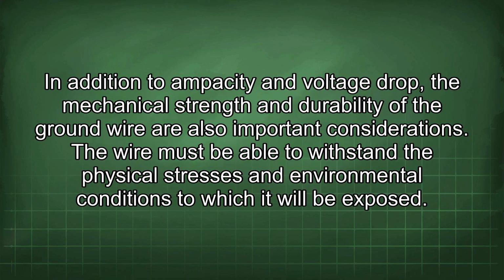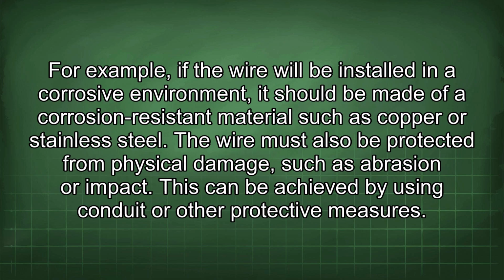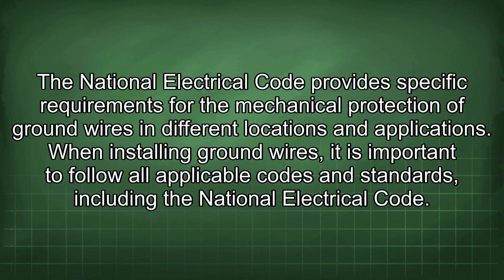In addition to ampacity and voltage drop, the mechanical strength and durability of the ground wire are also important considerations. The wire must be able to withstand the physical stresses and environmental conditions to which it will be exposed. For example, if the wire will be installed in a corrosive environment, it should be made of a corrosion-resistant material such as copper or stainless steel. The wire must also be protected from physical damage such as abrasion or impact. This can be achieved by using conduit or other protective measures. The National Electrical Code provides specific requirements for the mechanical protection of ground wires in different locations and applications.